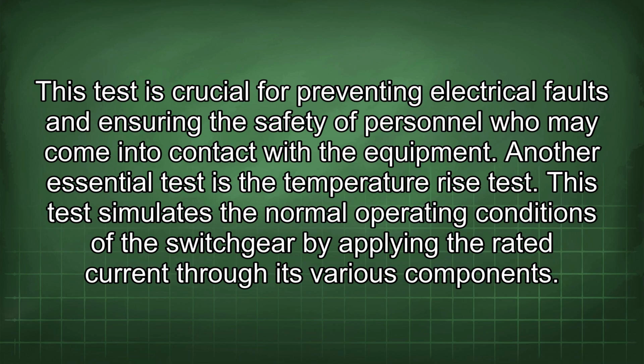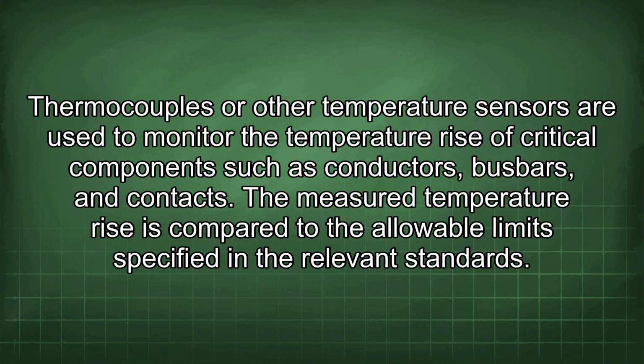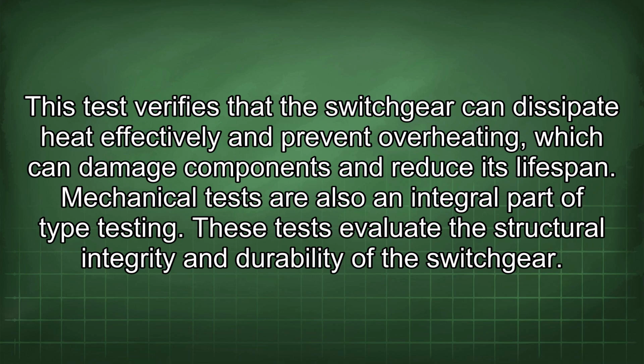This test is crucial for preventing electrical faults and ensuring the safety of personnel who may come into contact with the equipment. Another essential test is the temperature rise test. This test simulates the normal operating conditions of the switchgear by applying the rated current through its various components. Thermocouples or other temperature sensors are used to monitor the temperature rise of critical components such as conductors, busbars, and contacts. The measured temperature rise is compared to the allowable limits specified in the relevant standards.